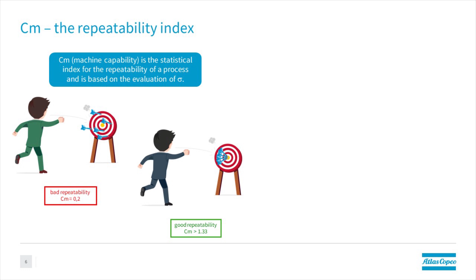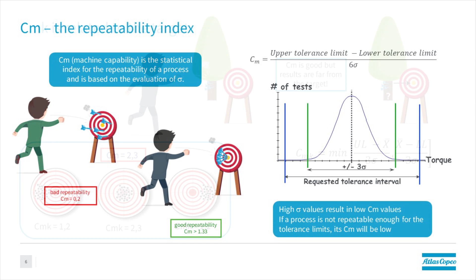In the chart here, we have counted the number of test results that have a specific value, and we have plotted them onto the chart. You can see that if the bell-shaped curve is a very lean one, you will have a high repeatability, and so you will have a high Cm value. The Cm value is only telling us how repeatable the results are with each other, but it's not telling us anything about whether we are on target or not.